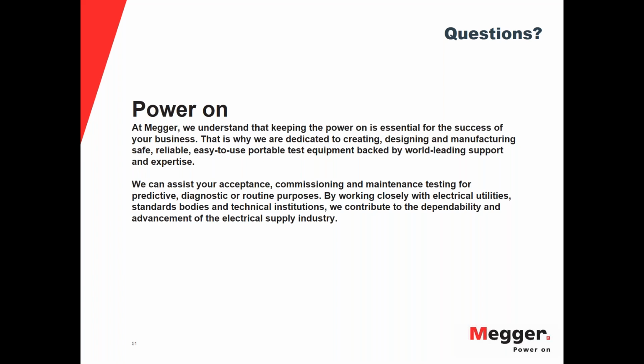Okay, so lithium ion batteries, definitely they are a new technology that is starting to show up in different installations, different facilities. The cost of these batteries is still a little bit prohibitive for the substation world. However, we are starting to get calls from customers asking how to test these batteries. Related to capacity testing, the test will be the same as we just described in the general concept. We want to discharge the battery down to a minimum voltage and check if it is giving us the capacity that is on the nameplate, or how that capacity is degrading.